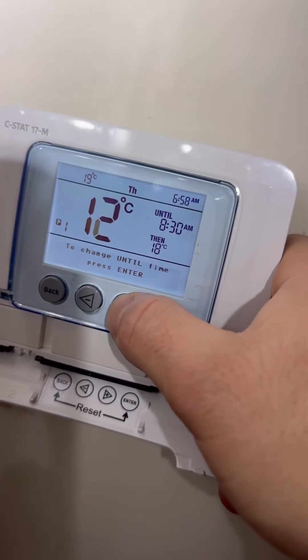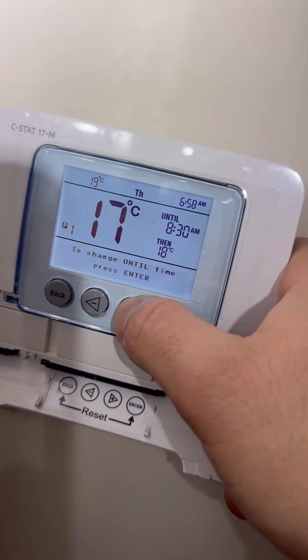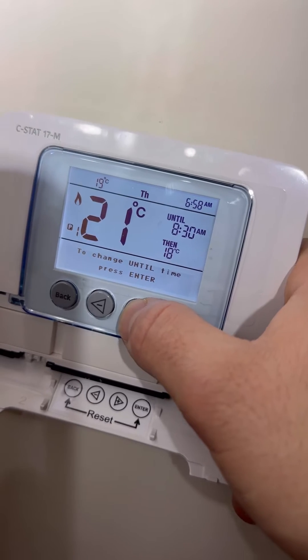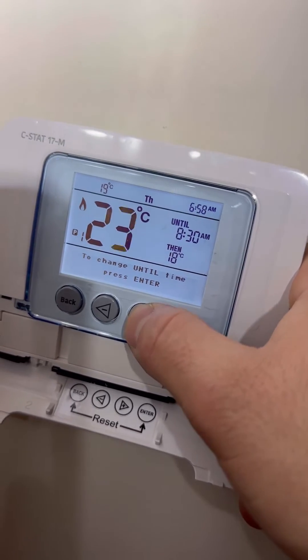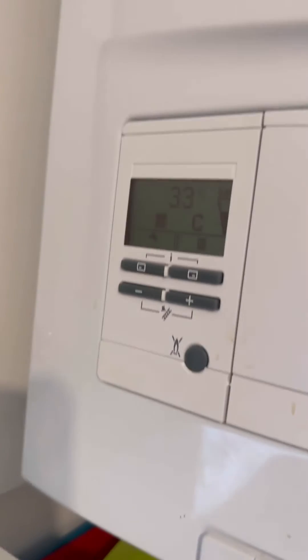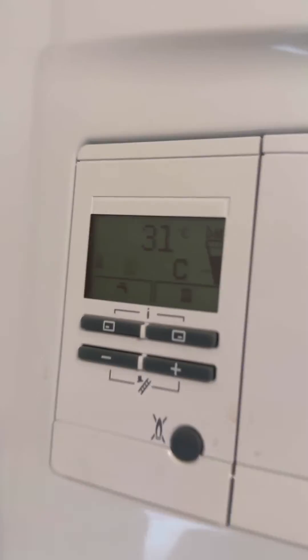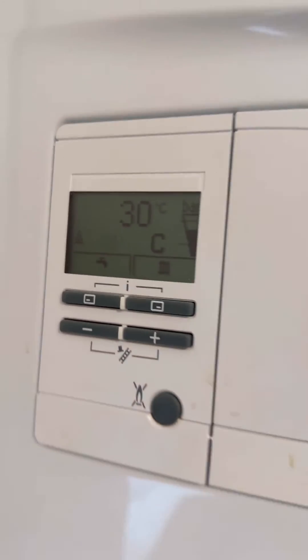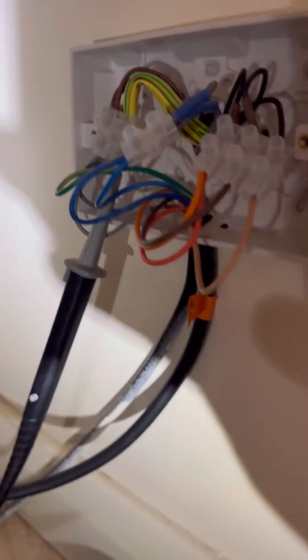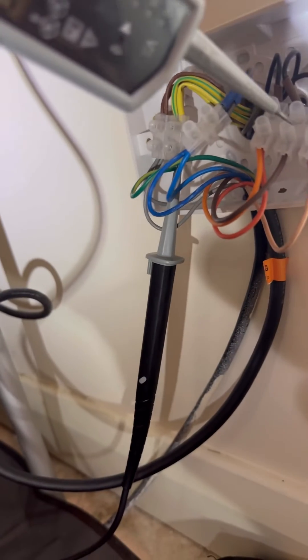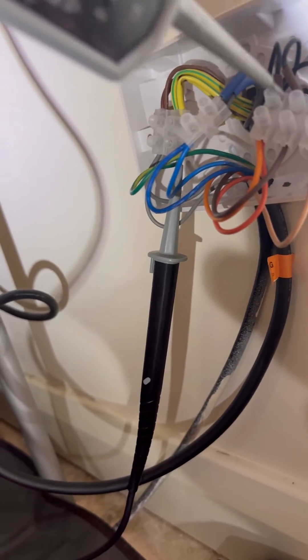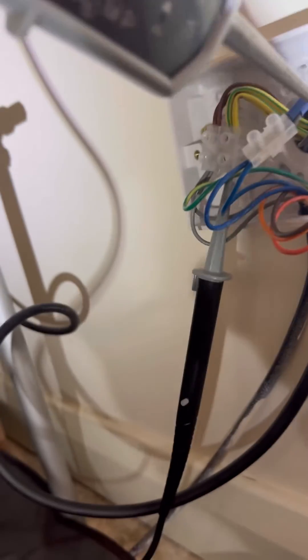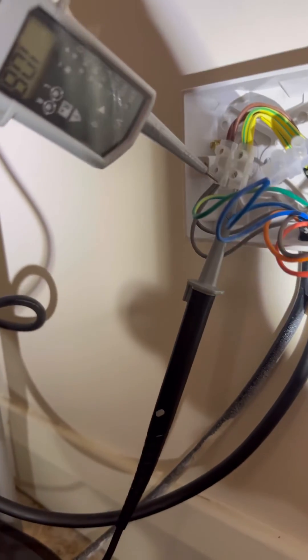Start calling for the heat on the stat downstairs. Boiler picks up the demand, starts firing. But that's not enough for me. I want to go back upstairs and just electrically test it. We turn the stat up downstairs, we're getting 240 now to the zone valve, that opens the valve, sends it back on orange to fire the boiler. Happy days.